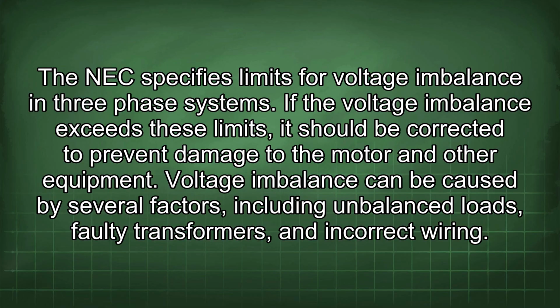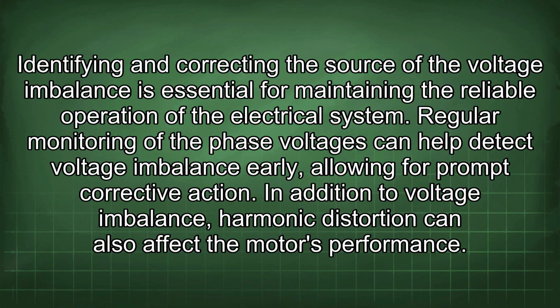Voltage imbalance can be caused by several factors, including unbalanced loads, faulty transformers, and incorrect wiring. Identifying and correcting the source of the voltage imbalance is essential for maintaining the reliable operation of the electrical system. Regular monitoring of the phase voltages can help detect voltage imbalance early, allowing for prompt corrective action.